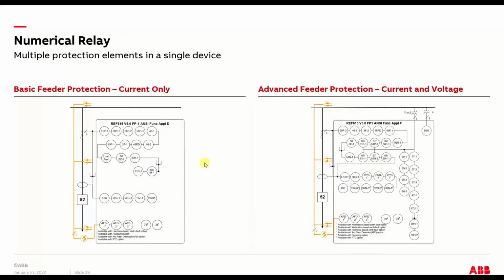So you actually have essentially what is a long time, short time, and then a true instantaneous setting all on this relay. And then here, just real quick, these are examples of modern, current day relays, and the circles in them kind of just give you a feeling of the number of protected devices you can get all in one box. This is a really basic numerical relay, and you've got your 50, 51, all three phases, plus ground current, neutral. This AFD is additional functions for arc flash detection. So you have basically all these devices built into one box.